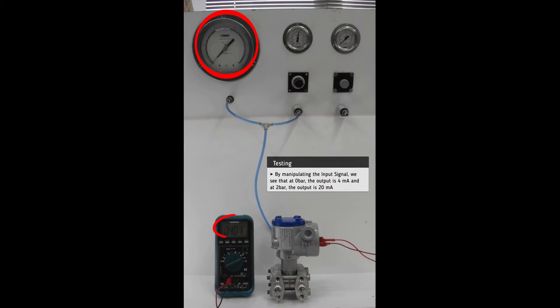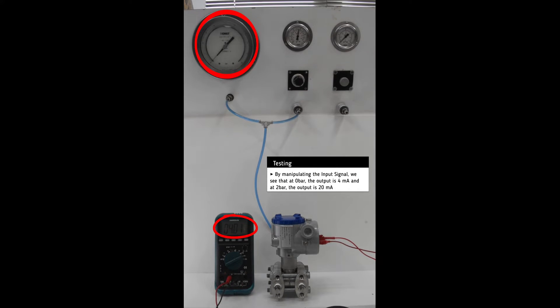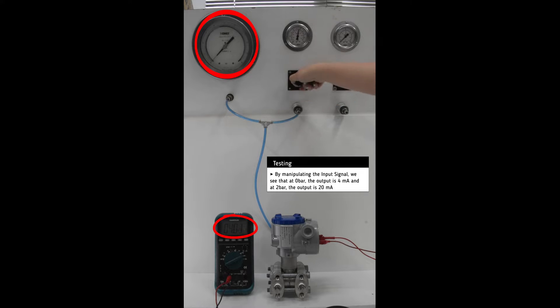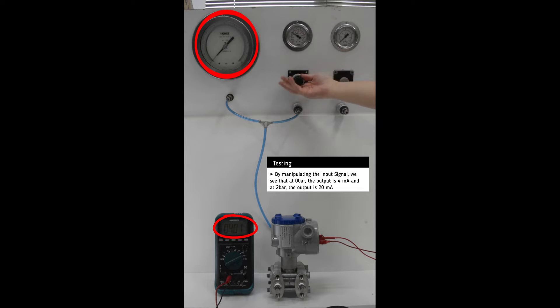By manipulating the input signal the unit reacts accordingly and we can see the four milliamp output at zero bar and the 20 milliamp output at two bar.